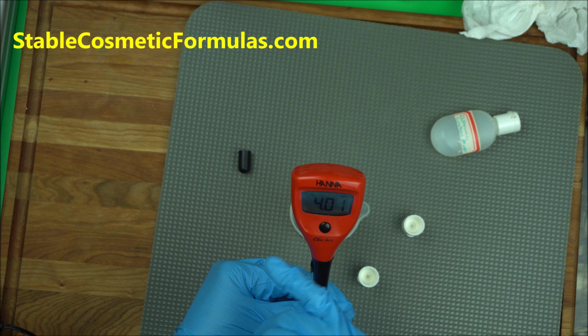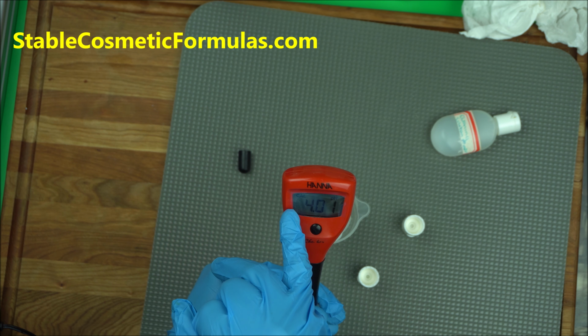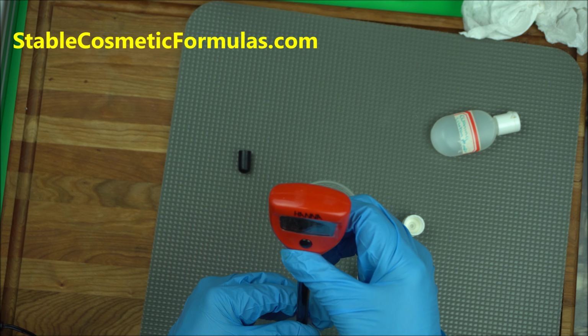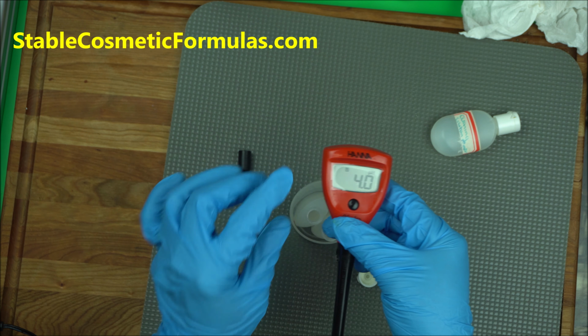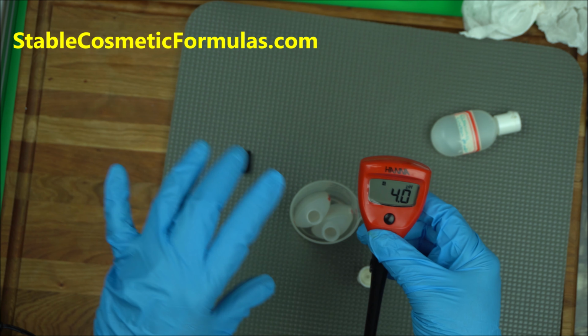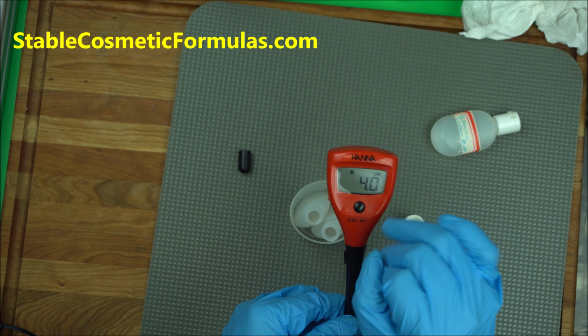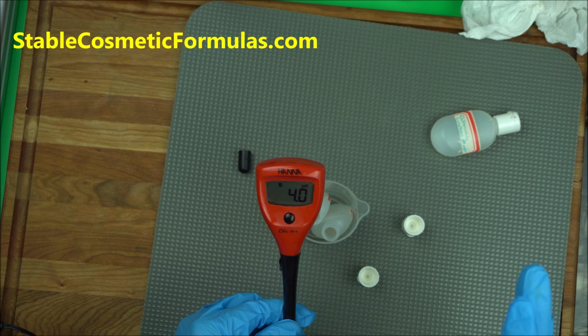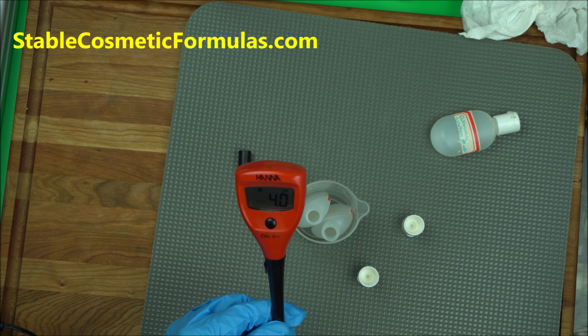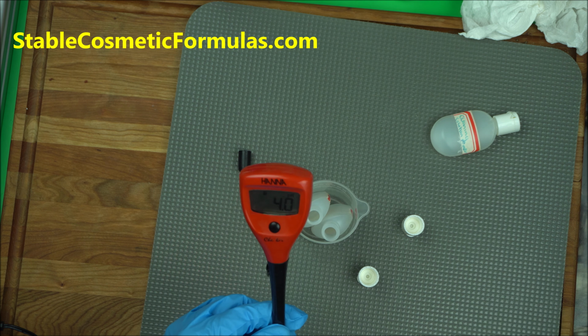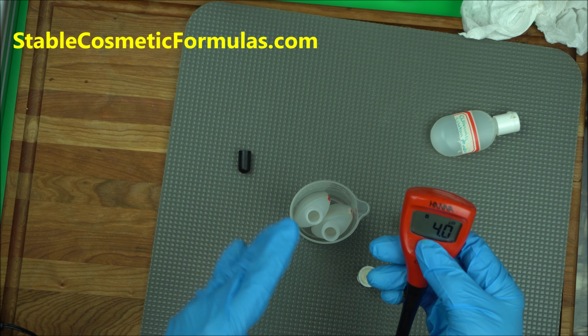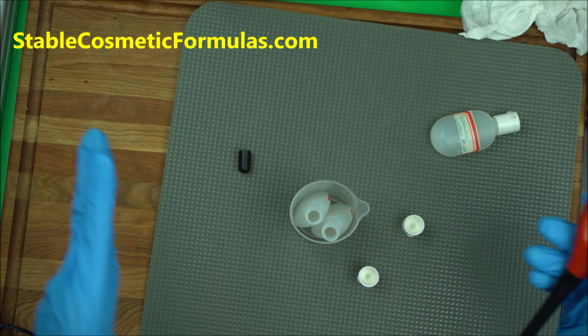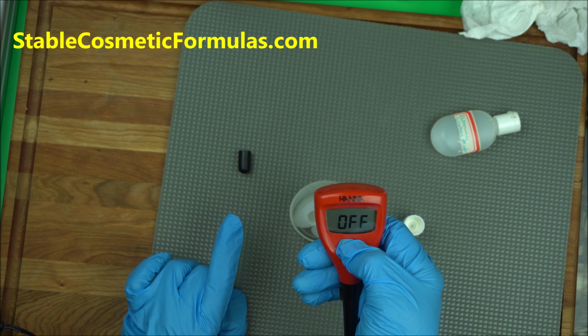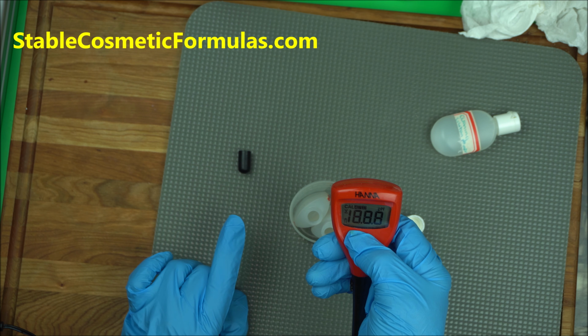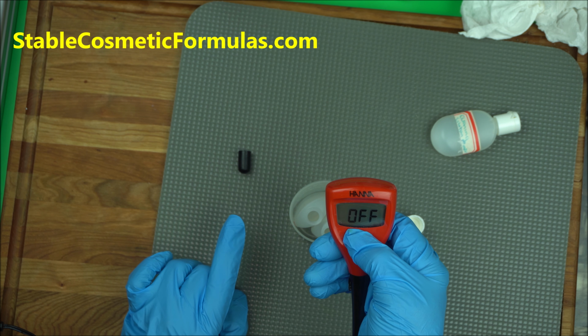So you're going to wait for that. When you are calibrating, watch this indicator here. So now it's going to tell you to stop. In this case, this is a good one to show you. I only have 4.0, because when it pointed me to do 7.0, I was low. So now, because I only have 4, and I have to calibrate between 4 and 7. If you make other skincare products where the recommended pH goes up to 10, you have to have a 10 buffer solution. But right now I have buffer solutions of 4 and 7, because my pH range is between those. I don't make products that go up to 10. So now it's 4. This is wrong. I'm going to turn it back on to start the calibration all over again. I'll have to start the calibration all over again.